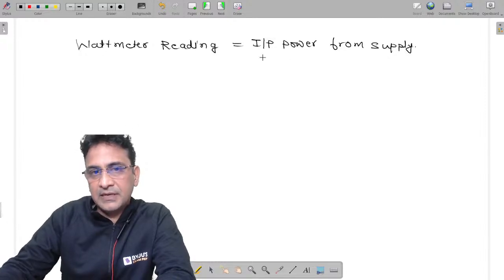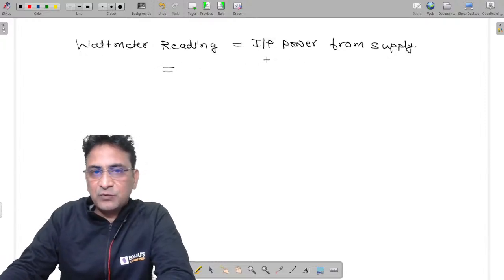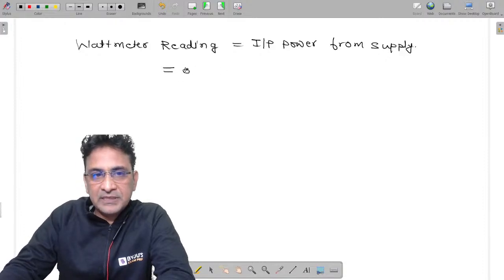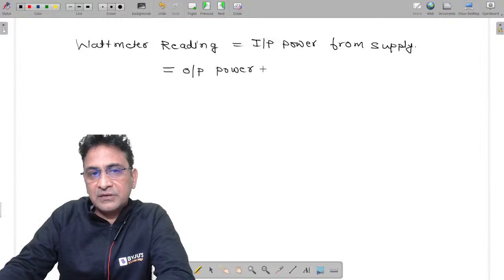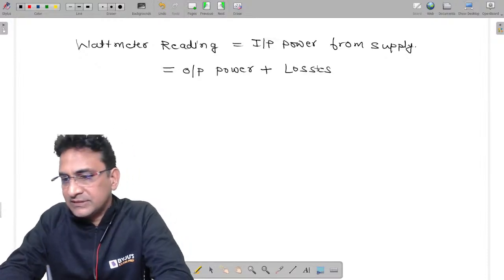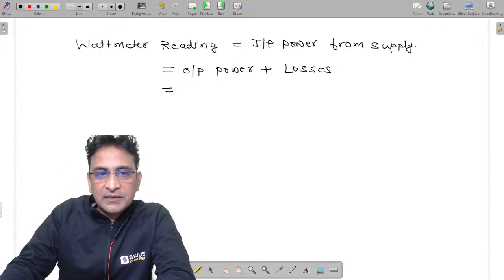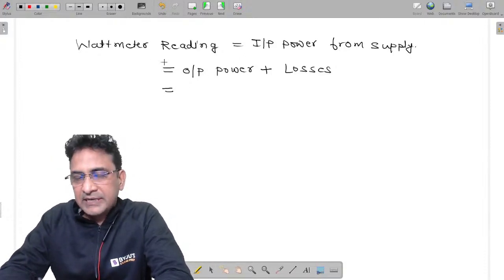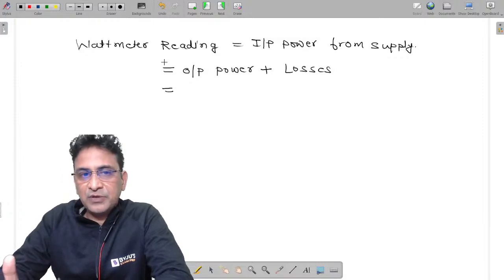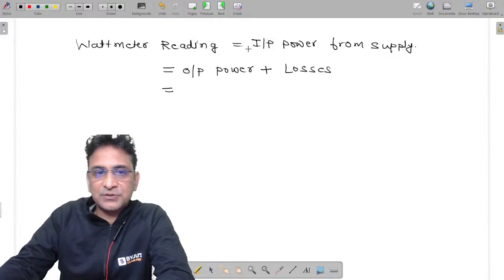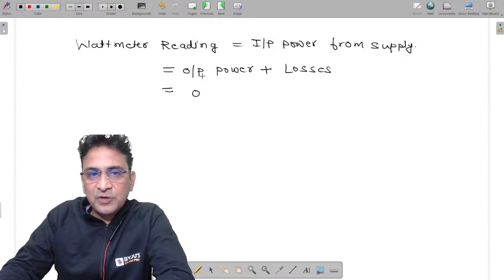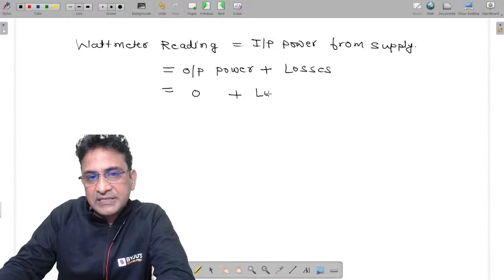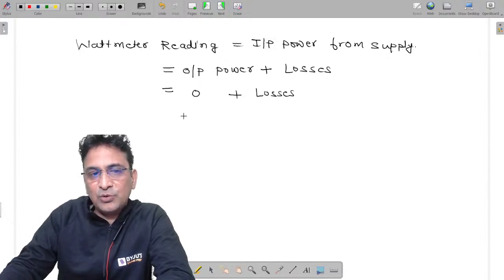Is it clear? And what is the input power? Whatever power we are taking from the supply, it would either be available at the output or it would be converted into losses. So input power is nothing but output power plus losses. So what is the output power? Because my secondary side is open circuited, the current flowing in the secondary side is zero. So when current is zero, the output power will be zero. So the wattmeter reading shows only the losses that take place during the no load time.